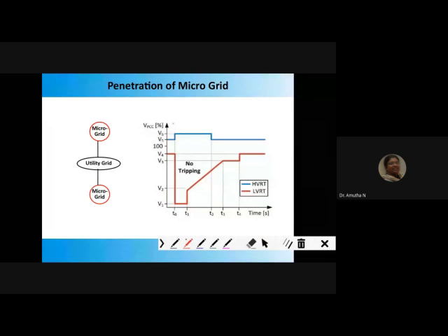This region and this region are the regions where the distributed generators can be disconnected, but in the region available between this high voltage curve and this low voltage curve, it should not be disconnected. So these two conditions it has to satisfy.